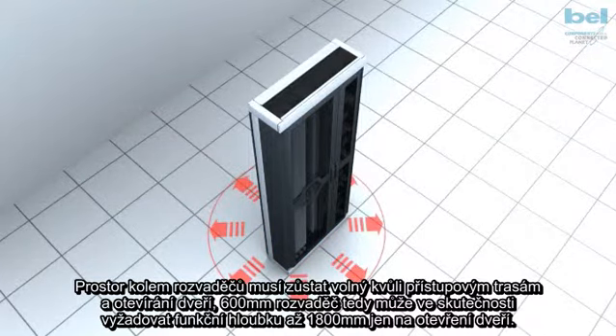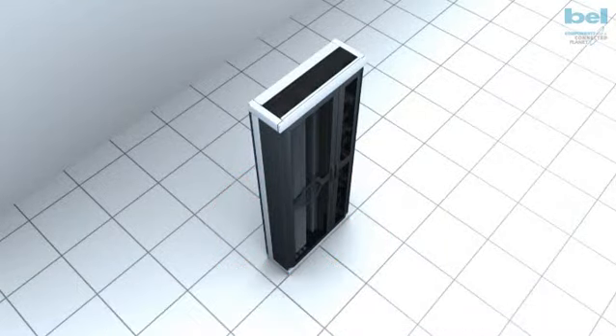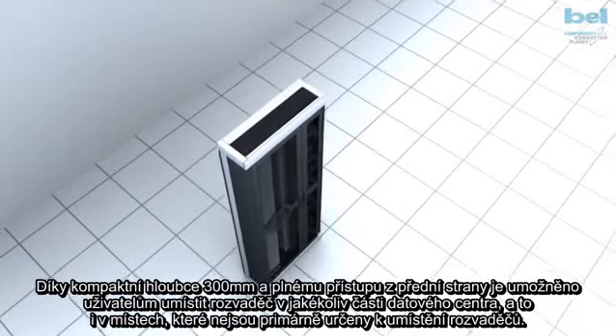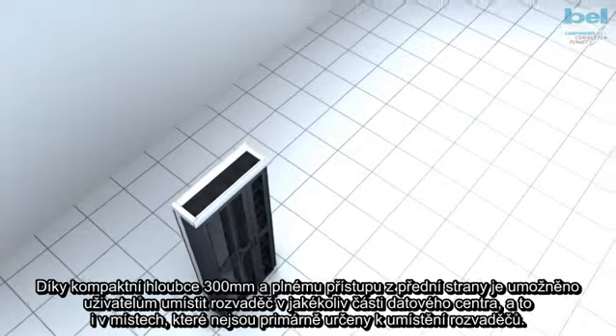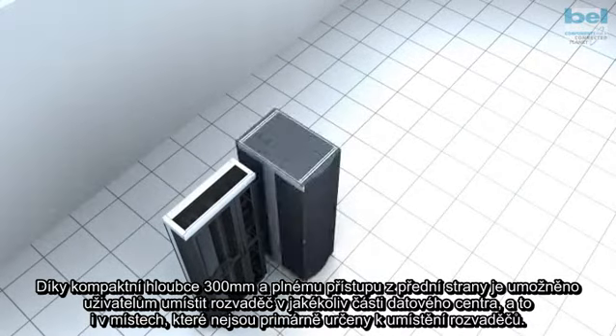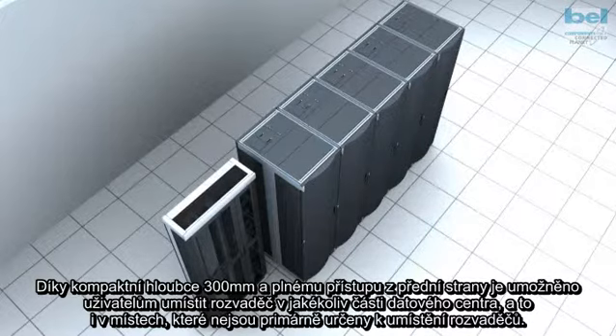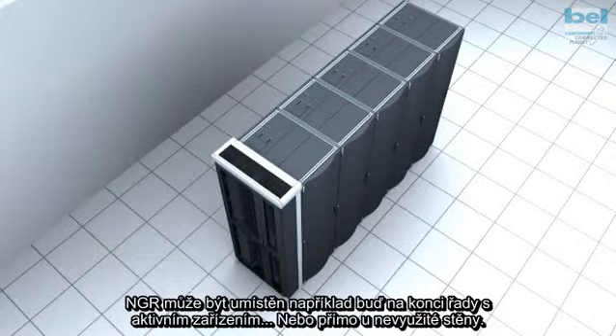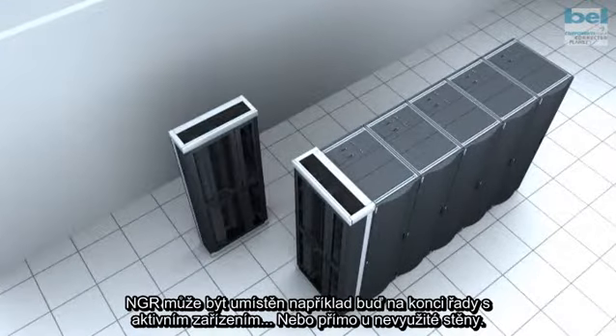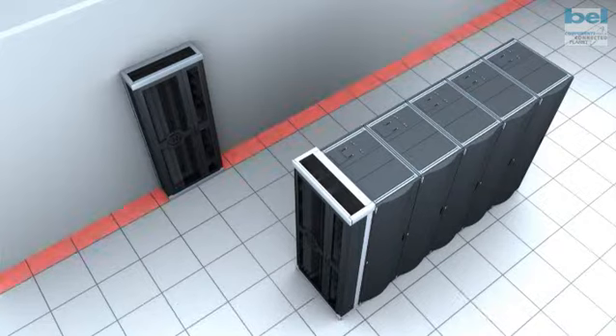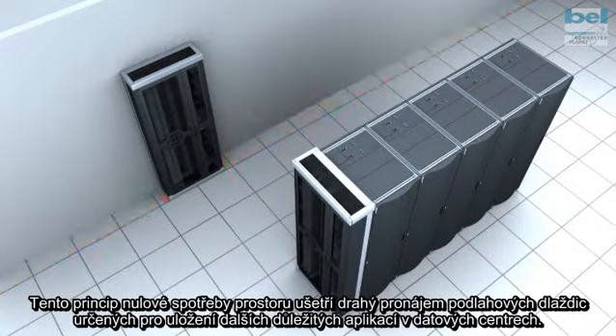Maintenance space around the cabinet has to be kept free for walkways and door clearance, and therefore a 600mm cabinet can actually require a functional depth of as much as 1800mm just to open the doors. The NGR's compact 300mm depth and full access from the front side allows users to position the rack in an area of the data center not generally used for rack placement. For example, the NGR can be positioned either at the end of nearby equipment rows or directly against an unused wall. This principle of zero space consumption ensures that premium-priced floor space is always kept available for other important data center applications.